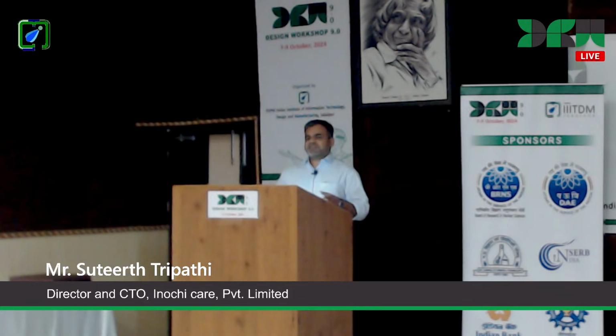But once we reached the months of December and January in Delhi, the flow rate started to drift apart. It would give the correct flow rate during the morning cycles when we were present, but recording the flow rate during the night, once we came back, we saw that around midnight the flow rates would change slightly. So we identified that these components were temperature dependent.